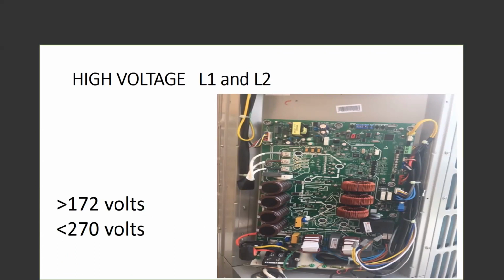I tell people all the time that this board is a brain. And so as we start to drop toward that 172, this system will actually deregulate itself. If it's a 3-ton or if it's a 5-ton, you're not going to get 36,000 BTUs of capacity or 60,000 BTUs of capacity out of it. It will start to deregulate itself, trying to push BTUs to the structure or remove BTUs from the structure. But it will not burn itself up. It will deregulate itself, taking the compressor down in hertz ratings as we get toward that 172.